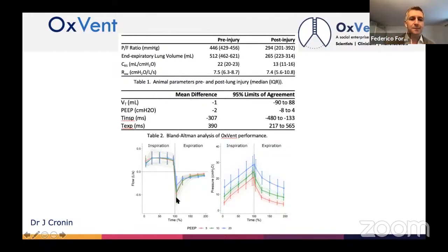And then during expiration, one of the things that has been improved since was that you see at the end of expiration, there's still some residual flow, and that is not desirable in mechanical ventilators because it could be an issue with the patient. And so if the ventilator does show some residual flow, it's not clear whether it's the ventilator or the patient from a clinical perspective. And the end expiratory pressure was reasonably within the target range, a bit lower than we had said.